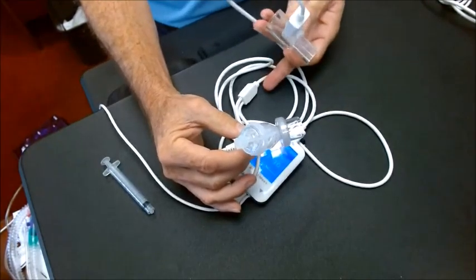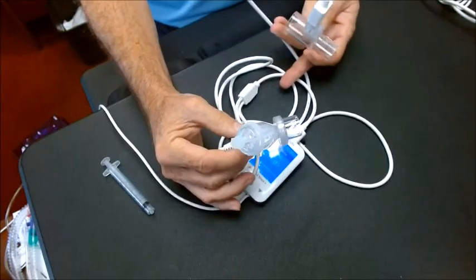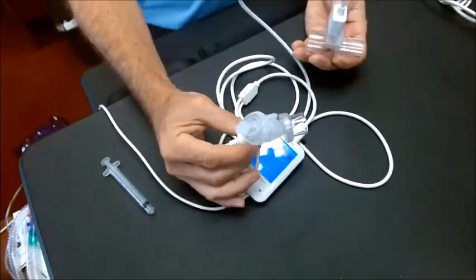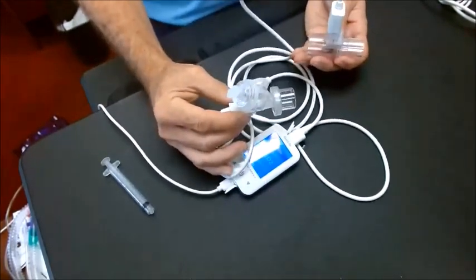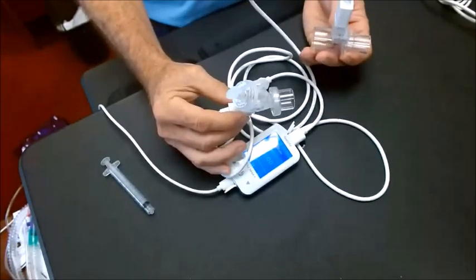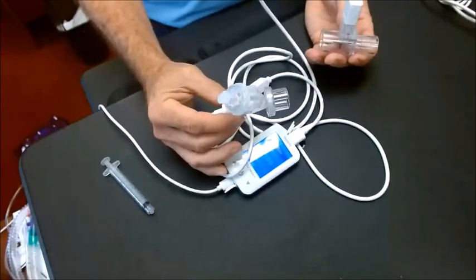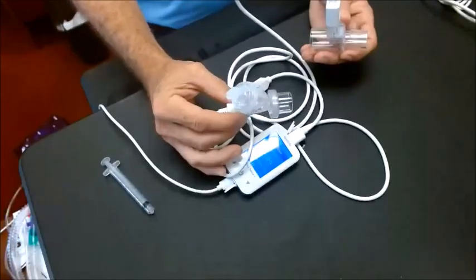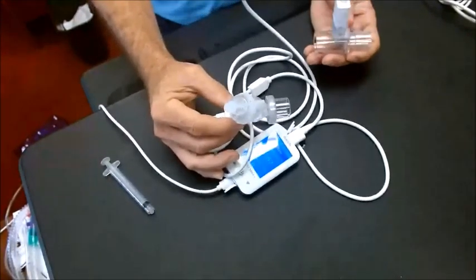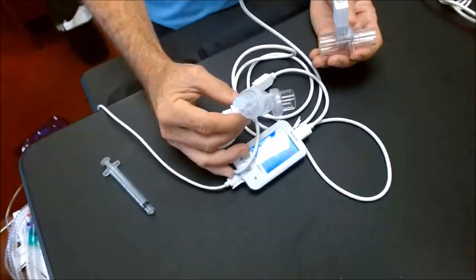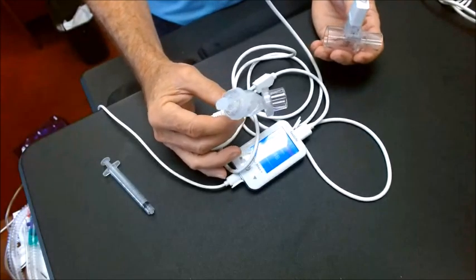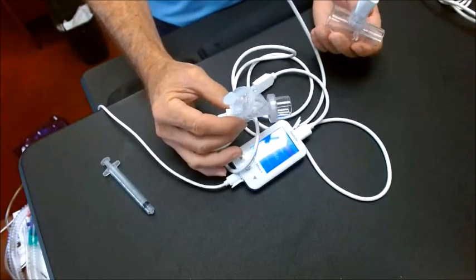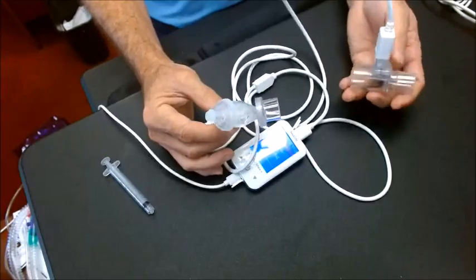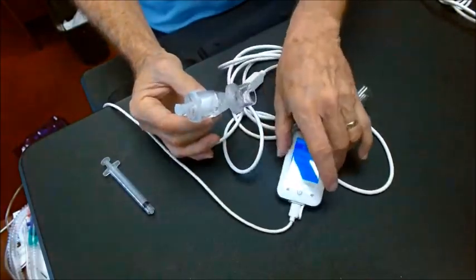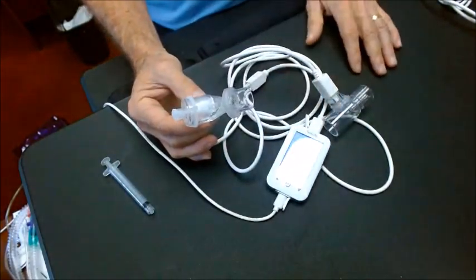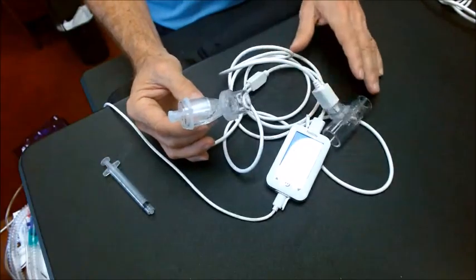It also requires what we call a Y cable. The Y cable will do basic continuous, and then if you attach a flow sensor, it'll convert it to breath actuated mode. So we have basically an entire new mode that can be at the fingertips of a respiratory therapist that could have some significant clinical advantages. So that's kind of a quick overview of the AirICU Max Plus controller.